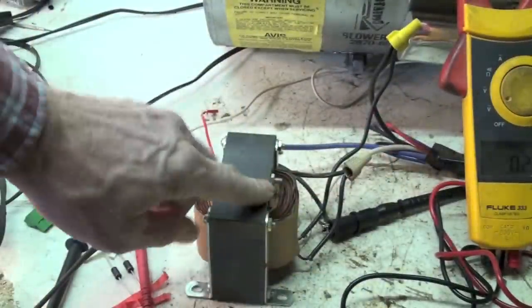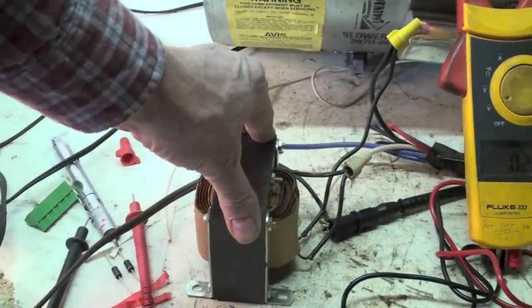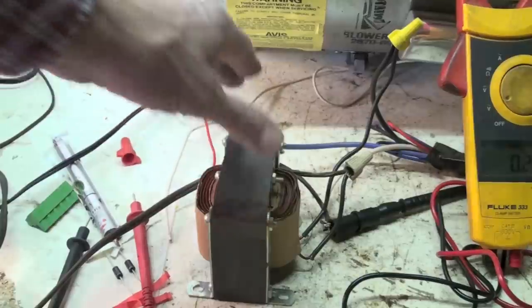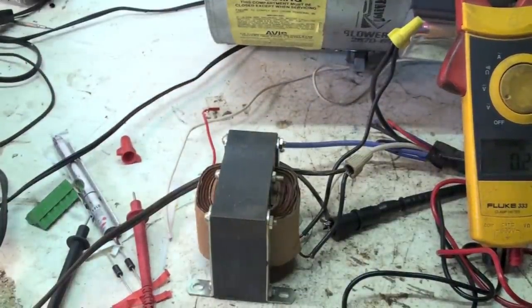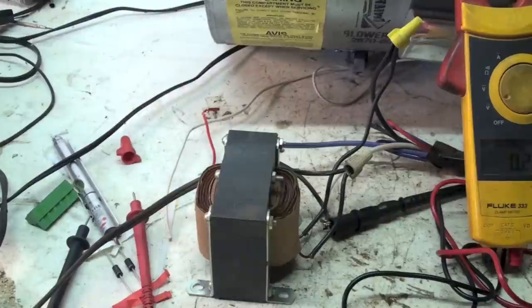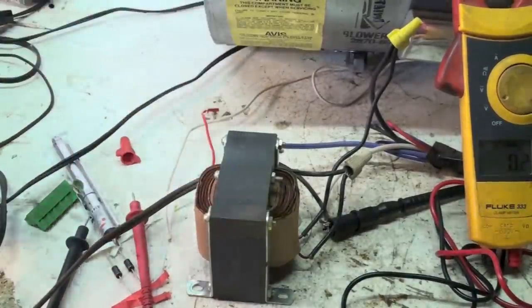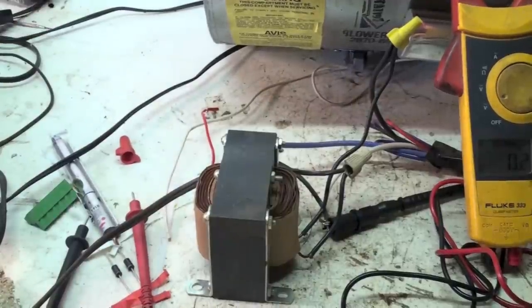So the choke coil has reduced the voltage coming out by inductive reactance. It has not increased the amp draw. The amp draw did not go up. The amp draw went down. Usually on a motor it will go up if you reduce the voltage.